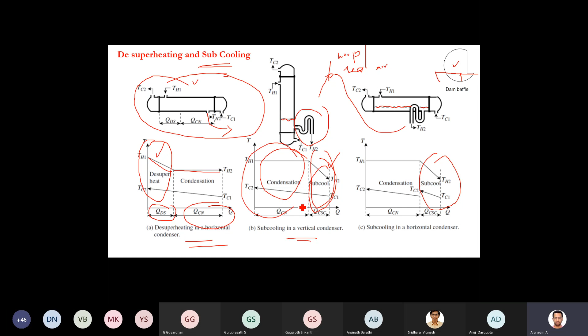Then you can see that with phase change, when desuperheating and subcooling are accommodated with the condensation, then how the estimation of area can be done. The exchanger has to be divided into different parts like desuperheating zone, condensation zone, and subcooling zone. So zone-wise we have to do the calculation procedure. Okay, because the desuperheating zone will be like a heat exchanger without phase change. Similarly, the subcooling zone is again heat transfer without phase change. Only in condensation does the phase change occur. So accordingly, we have to modify the design equations. Okay, you can use the Sieder-Tate equation for the desuperheating zone and subcooling zone, and you have to use the Nusselt equation to calculate the heat transfer coefficient of condensate in different configurations. Okay.